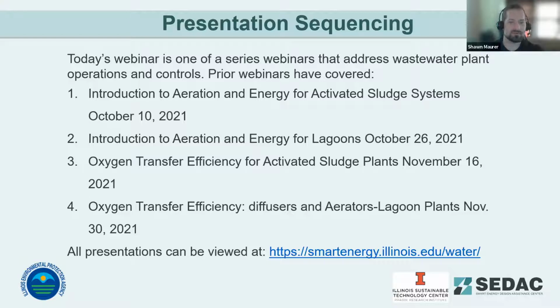Just to review what we've covered previously in our presentation sequence: we started off covering aeration and energy for activated sludge and lagoons, looking at VFD control of blowers and optimizing the connection between the diffuser system and the blowers. Then we looked at the actual efficiency of diffuser systems and mechanical mixing systems — how to get oxygen into the water — in the second part of our series. Now we're going to look at control systems, digging into how the SCADA system interacts with those aeration systems and how to optimize system control.